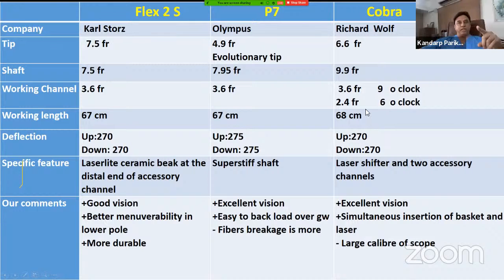Cobra has two channels. One channel is 3.6 French and the second is 2.4 French. Also, this scope has a laser shifter. It is fixed at the 9 o'clock position over the 3.6 accessory channel. So you can pass a laser fiber through that laser shifter, and then you can fix the fiber so that there is no accidental movement of the fiber while you are operating. You can advance or withdraw the laser tip by rotating a knob over it.